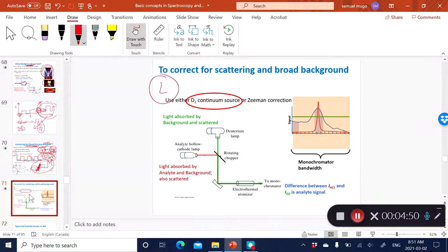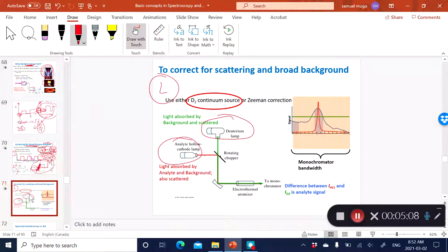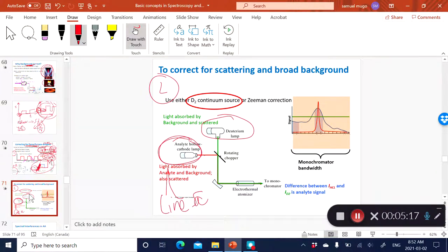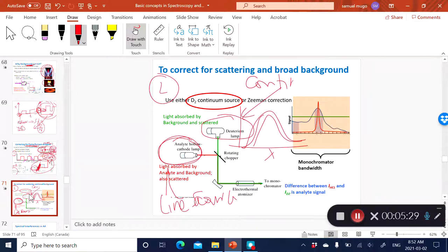Another method of background correction is where you have two light sources: the hollow cathode lamp as your analytical line source, and also a continuum-type light source such as deuterium. The hollow cathode lamp is a line source, whereas the deuterium is a continuum source, meaning the wavelength range is fairly broad. You can have a rotating chopper that blocks the light from the deuterium.